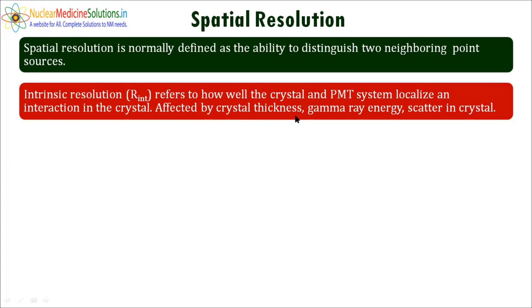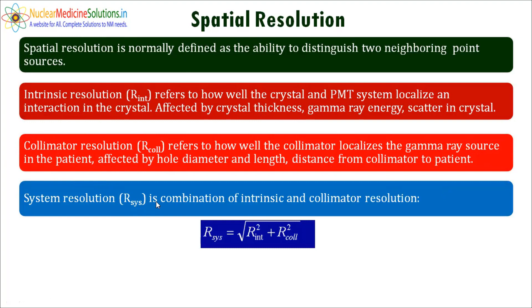PMT system localize an interaction in the crystal, and it is affected by the crystal thickness, gamma ray energy, and scatter in the crystal. Second comes the collimator resolution, which refers to how well the collimator localizes the gamma ray source in the patient, and it is affected by the hole diameter, length, and distance from the collimator to the patient. And the combination of the intrinsic and the collimator resolution is called the system resolution.